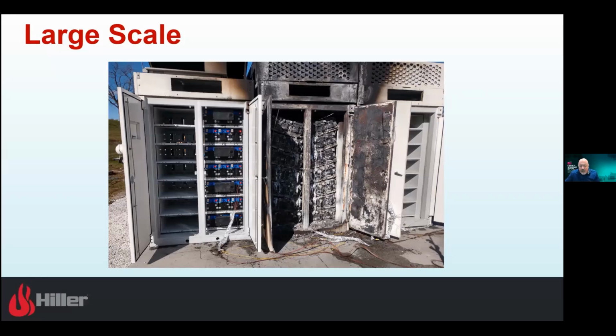What we require is a gas detector. If we put out a fire and see rising hydrogen levels, immediately we switch. Even if we dump that clean agent two seconds before, we automatically switch over to exhausting priority. Explosion becomes a higher priority than fire. We don't care about the agent that's in there.